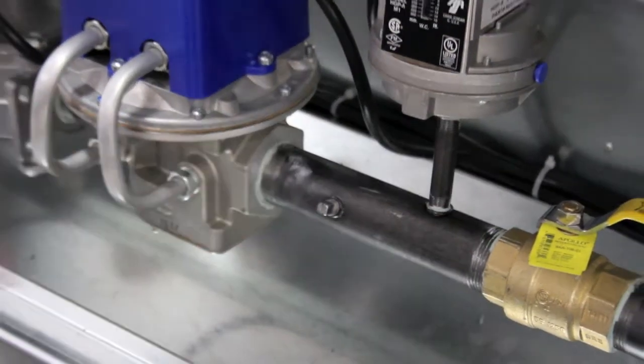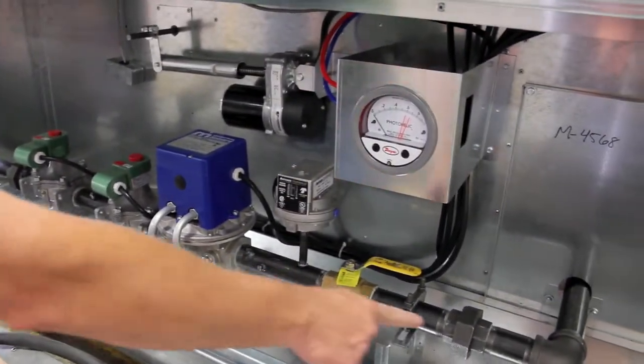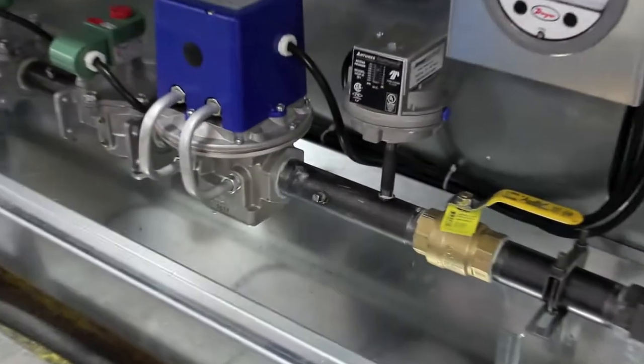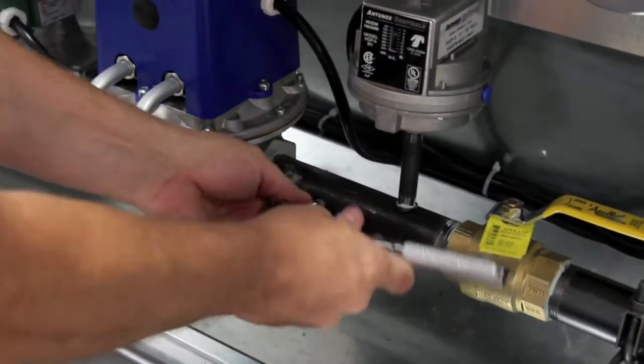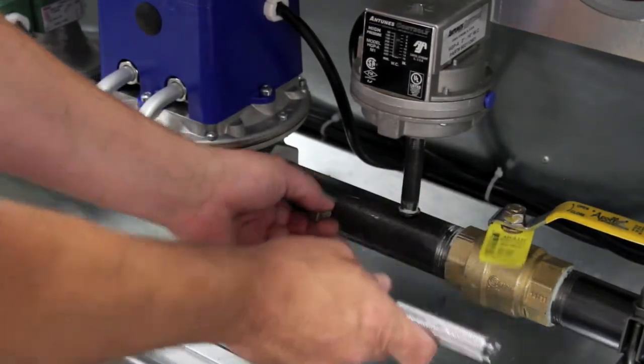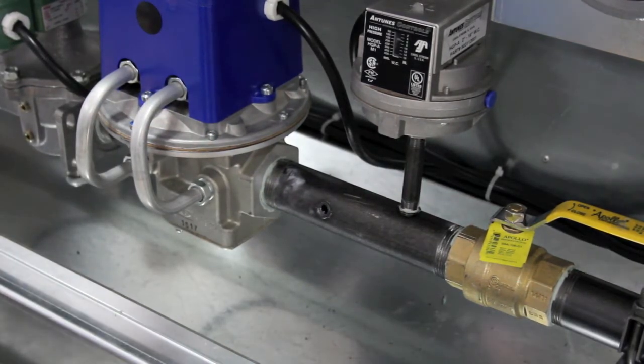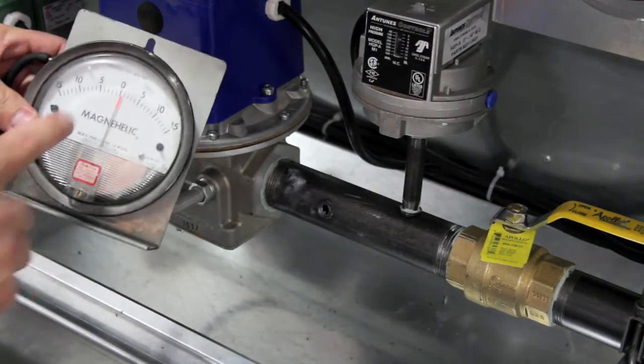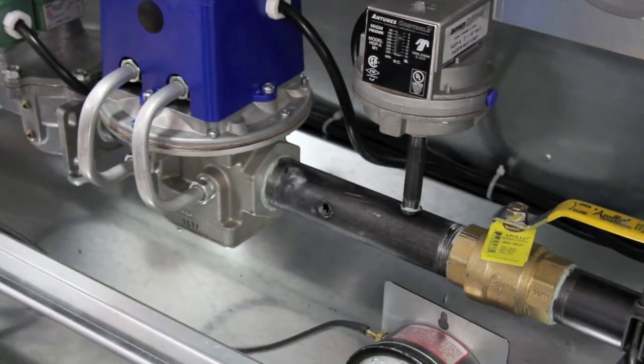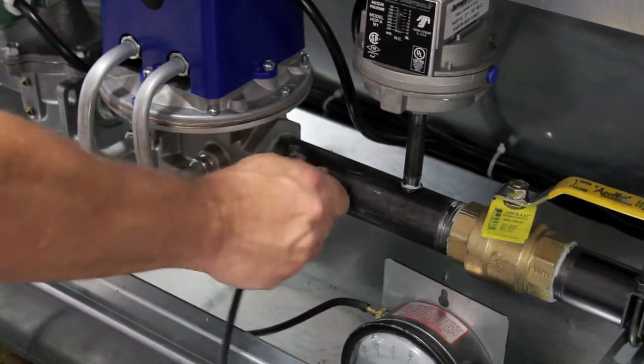Now connect your gas manometer. The gas pipe comes in on the left and goes through the gas train to your burner. The pipe plug that you will use is the closest tap to the burner. Remove the 1/8 inch pipe plug and install an inches gauge in this location — preferably a 0 to 15 inch gauge. As you see here, I am using a negative 15 to positive 15 Magnehelic. Simply connect the barb hose fitting in the hole and tighten.